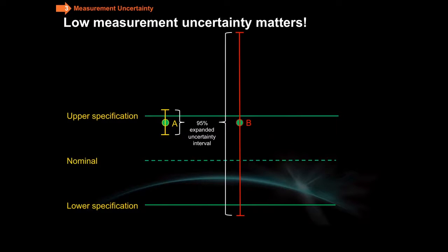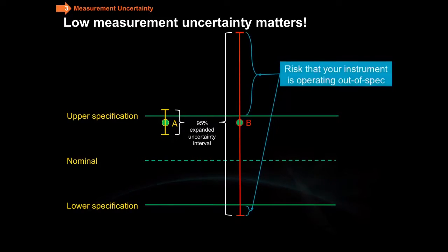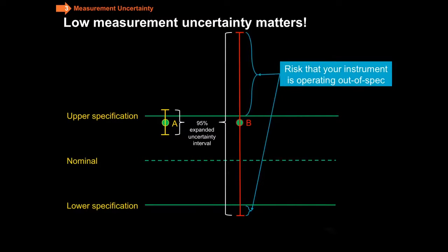Those are pretty different. If you were to look at the intervals outside of the specification, either above the upper or below the lower, those represent where your true measurement could be. And obviously if that's the case, then you measured the instrument to pass when in fact it didn't. So hopefully you can see having a smaller 95% expanded interval is a really important thing because that takes the doubt of where the true measurement really could be and keeps it to a minimum.